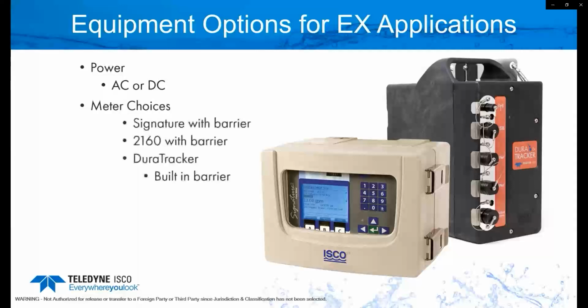Our particular meter choices would be a couple different ones. The one on the bottom would be the signature, and the signature has an external barrier. The signature is the electronics, and the barrier is the isolation to that environment. The 2160, one of the older style 2100 series platforms, can also be used in an intrinsic safe application. But one thing to keep in mind with anybody's equipment is sometimes the sensor is rated intrinsic safe, but the meter may not be. So if the meter is not rated intrinsic safe, you have to keep it out of the hazardous location, and the barrier will isolate it from that location.